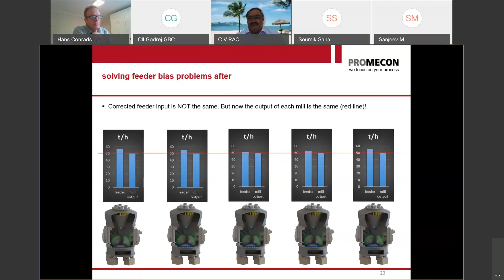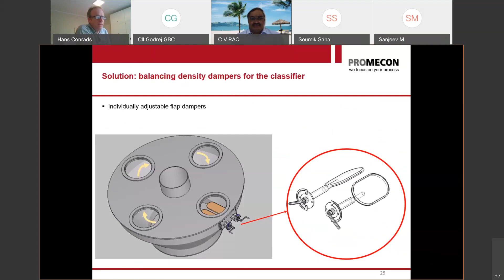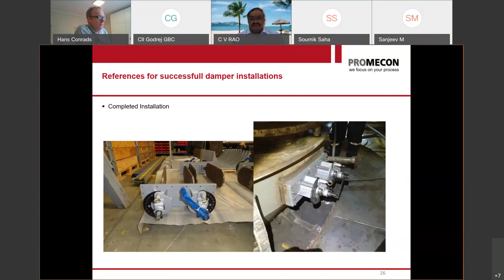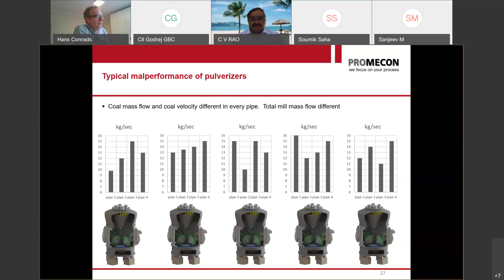Since we can measure the coal output on each pipe, we can also correct coal imbalances pipe by pipe. This is another big contribution to lowering NOx. We do that with an adjustable flap damper installed on top of the mill - it looks like this. Easy installation, and after installing it you can correct the imbalance burner by burner, before and after. This is how it looks in real life.